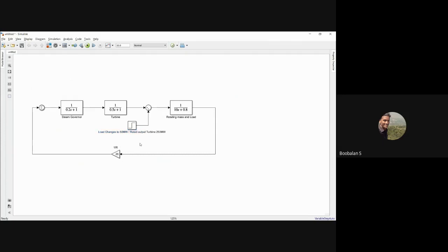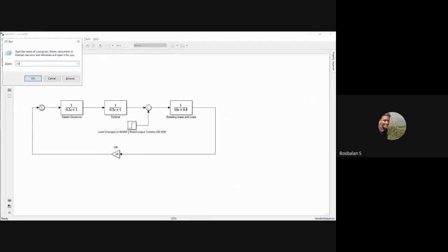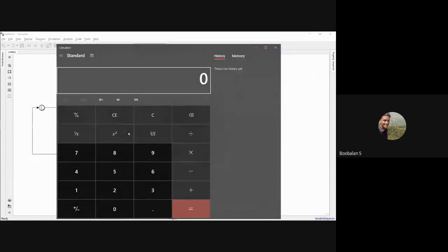Now we need to convert it back into per unit. We need to calculate in per unit what the maximum sudden change is. 50 megawatt is the change, rated output is 250 megawatt. So the value for that change is 0.2 per unit, since 50 megawatt out of total capacity 250 gives 0.2.